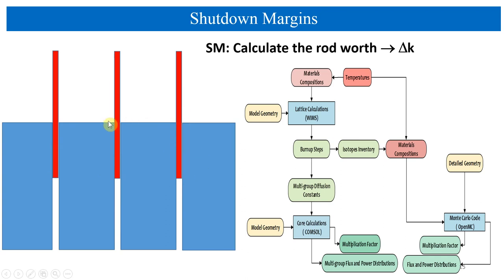These portions are just to compensate the excess reactivity in the core. During the cycle, I should be removing these control rods, or extracting these controls outside the core, until these control rods reach the top position, then I can stop the cycle and add new fresh fuel. The part of the rod which is outside the core at the beginning of cycle, we can call the shutdown margin, which is the negative reactivity available for safe shutdown.